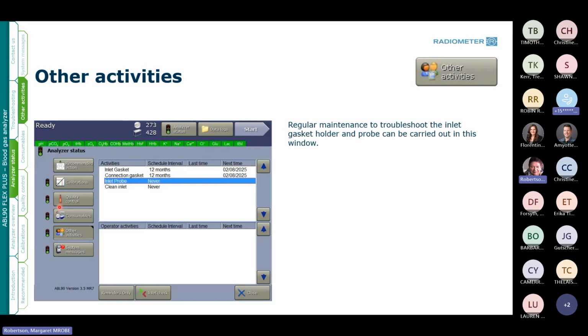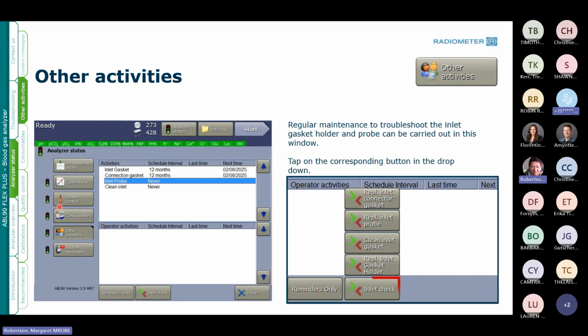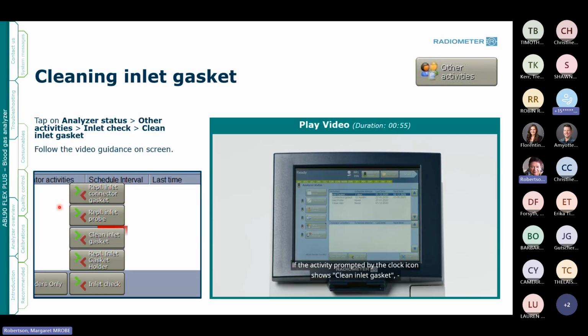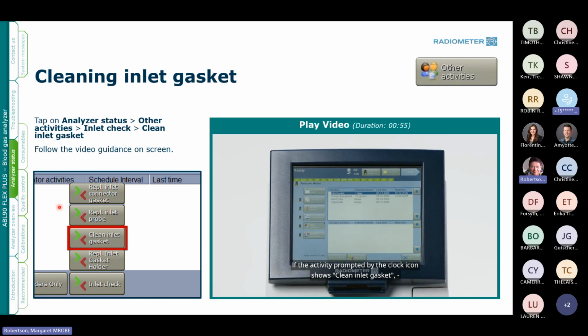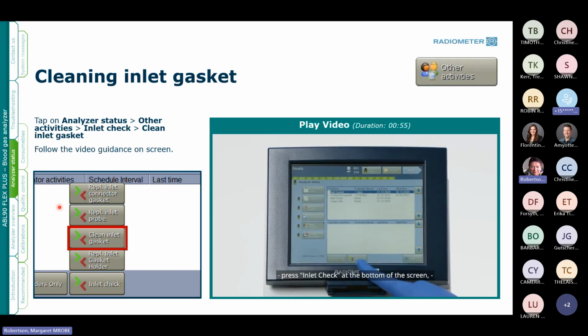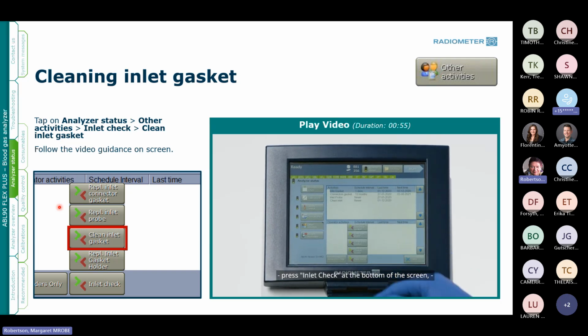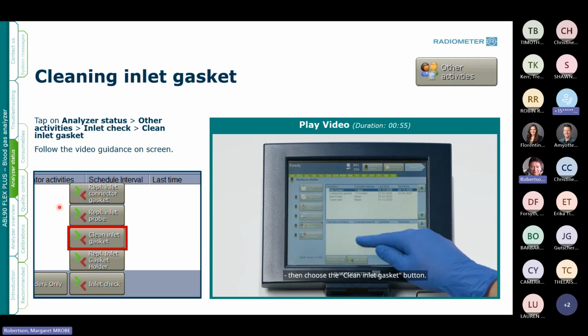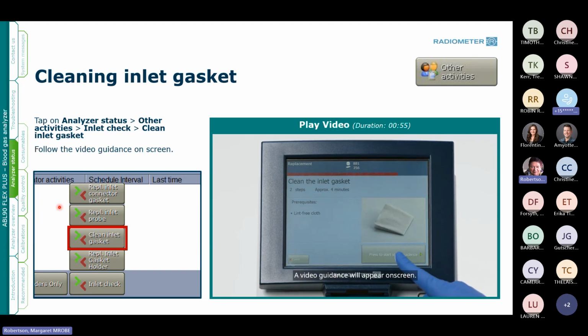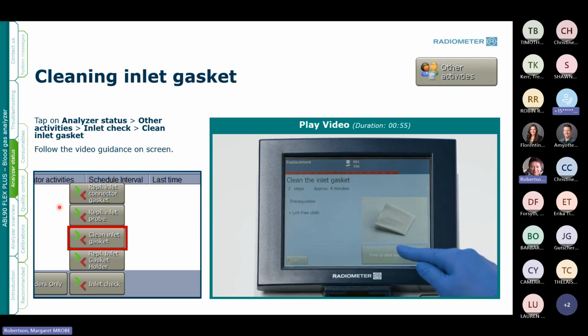And again, you're going to go into Analyzer Status. You'll look at the bottom, you'll see Inlet Check, which brings up a menu. And you've got several different options there, depending on what it is we're going to do. So the first thing we're going to do is clean the inlet gasket. The activity prompted by the clock icon shows Clean Inlet Gasket. Press Inlet Check at the bottom of the screen. Then choose the Clean Inlet Gasket button. A video guidance will appear on screen.